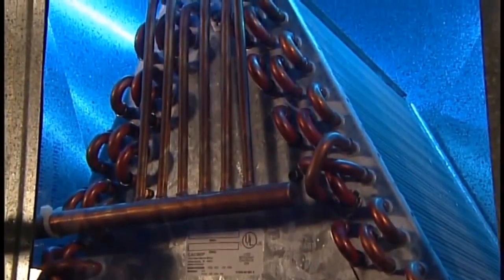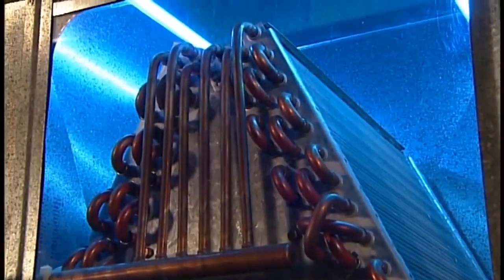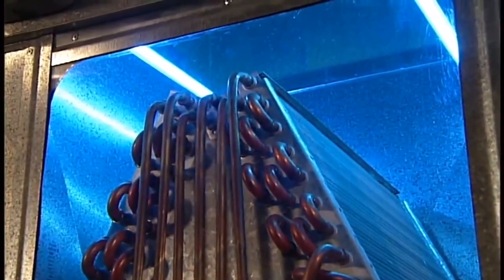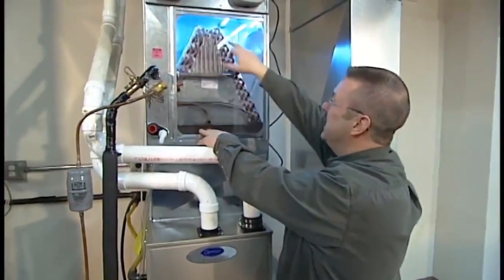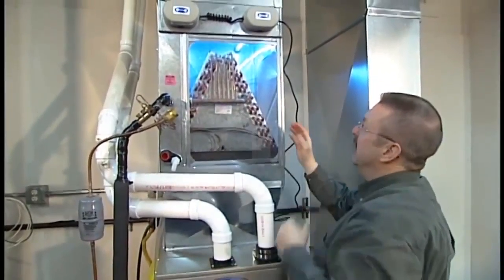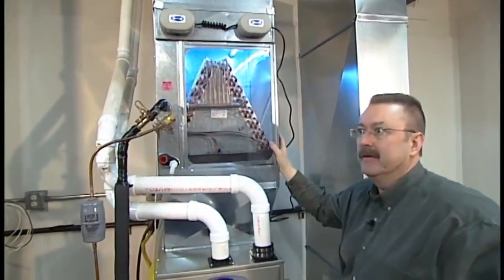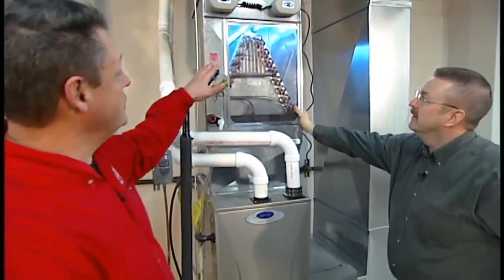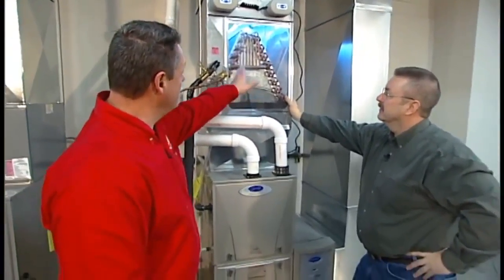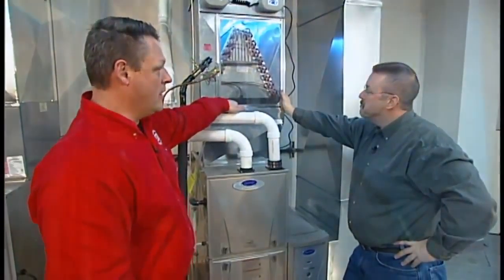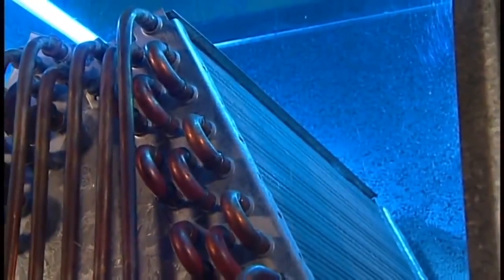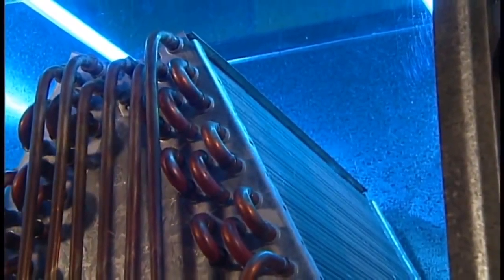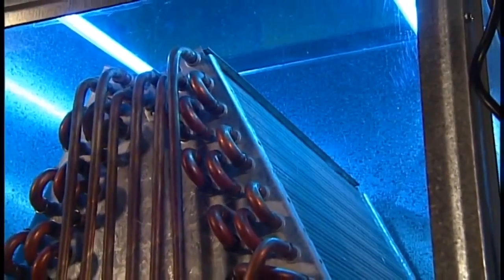One of the things I love about visiting your training facility, you get to see where you normally don't. And by that I mean, here's a plenum, you get to see the A-coil for the air conditioning system, and I also notice a couple blue lights up there. Yeah, those are actually UV lights that radiate onto the coil and the condensate pan to kill microbes that can grow on there, which does two things: keeps it cleaner and gives higher efficiency.